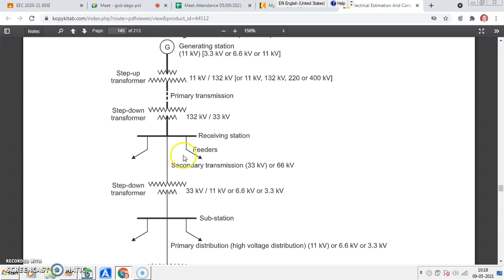Then again you have to step down, that is primary distribution, what we can say. So primary distribution is either 11 kV or 6.6 kV or 3.3 kV. Now as far as India is concerned, we don't have 3.3 kV and 6.6 kV. We have 11 kV and 22 kV. If you say the Pune region or Mumbai region, Konkan region, we have the high voltage distribution at 22 kV. If you say the Ahmednagar or Nashik region, we have the primary distribution of 11 kV. So that depends. Normally 22 kV is more efficient than 11 kV.